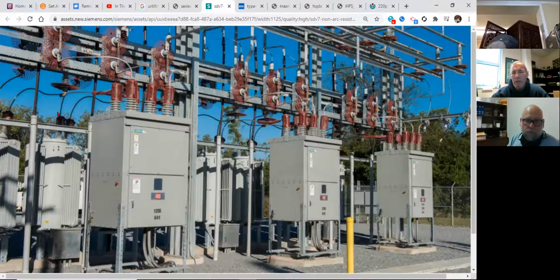If we have a feeder or line side fault, we don't want that to reach the transformer. If it happens on our line side, which has more exposure out there in the world, we don't want it to go through the breaker and then to the transformer. That transformer costs us a lot of money. We want to be able to sectionalize that portion of line with a circuit breaker.